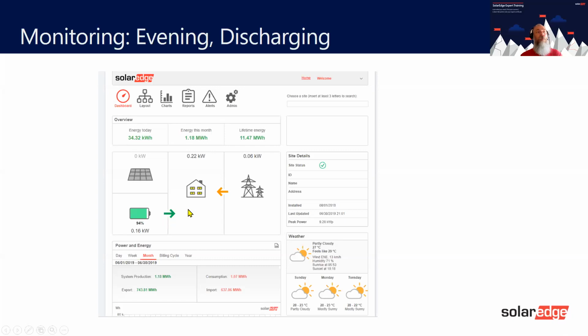There will be a time where you still get a little bit from the grid, and that's purely depending on how your loads react. If your loads react very, very quickly, like you go in and turn a kettle on, or you turn the oven on, it's going to be a little bit quicker for the grid to react than the battery to react. So don't be alarmed if you see both of these at the same time and it using a small amount.